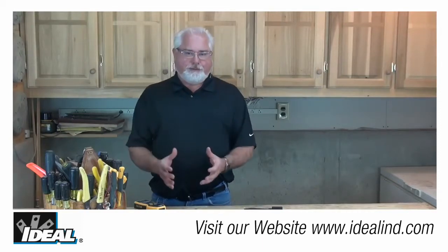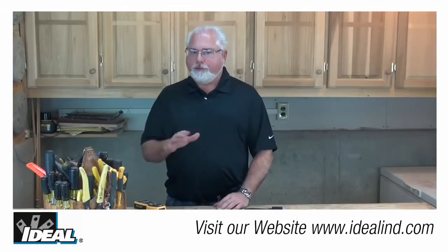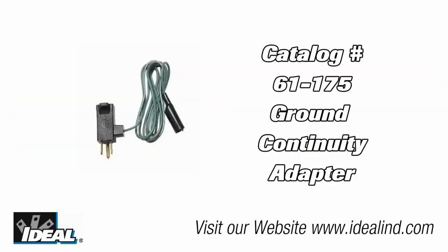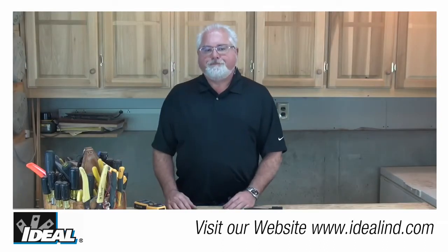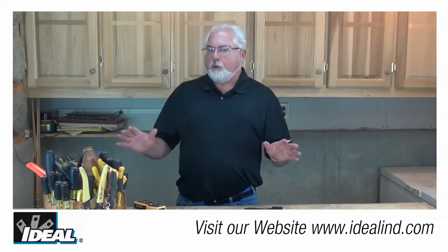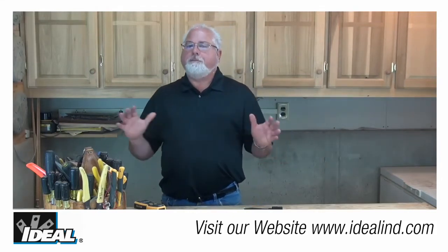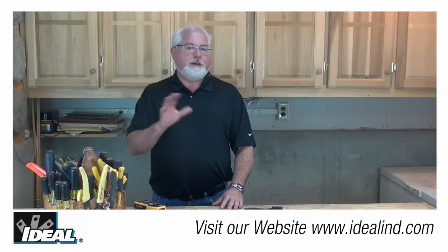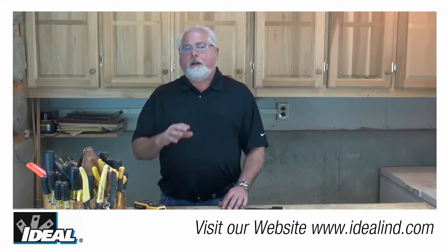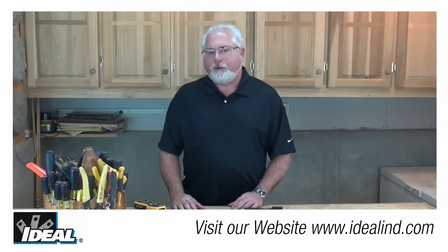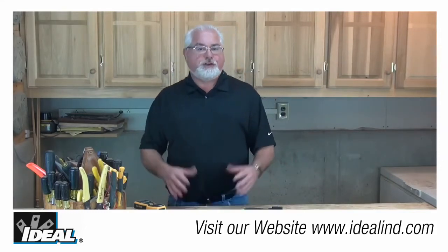Now, note, to test a GFCI device in a 2-wire system where there is no ground, we're going to ask you to use the Ideal 61-175 ground continuity adapter. Now, you're going to connect the alligator clip on the adapter to a ground source, which could be structural steel in a building, a metal gas pipe, or again, a metal water pipe. Now, also, all appliances or equipment on that circuit being tested should be unplugged to help avoid any erroneous readings that might happen.